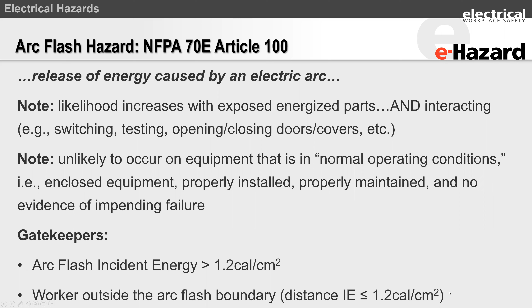What NFPA 70E also states, and this is very interesting, is that an arc flash incident is unlikely to occur when equipment is used in its normal operating condition. The big three that folks talk about are: properly installed, properly maintained, and no evidence of impending failure. I'll talk about proper maintenance in a short while, but remember the gatekeepers: the arc flash energy needs to be greater than 1.2 calories per square centimeter to ignite general, civilian-type clothing, and the worker needs to be inside an arc flash boundary for this hazard to be present. Once you get outside of the arc flash boundary, the energy has dropped substantially and will probably not ignite non-arc rated clothing.